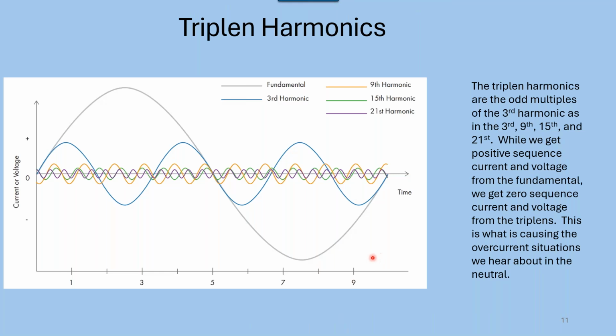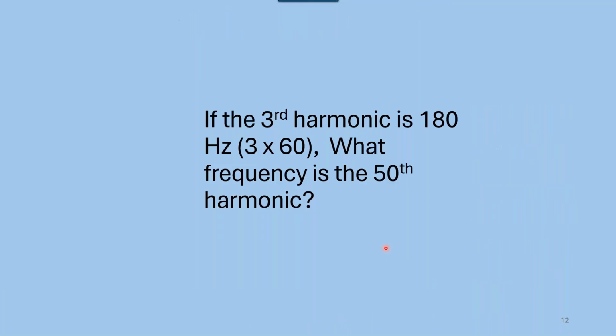Here I'm just showing the triplen harmonics. As I mentioned, those are the third, ninth, the odd ones. And that's where we get the zero sequence currents and voltage from the triplens. That's causing the overcurrent we talked about in the neutral. Okay? So when people ask you that, that's what it is.